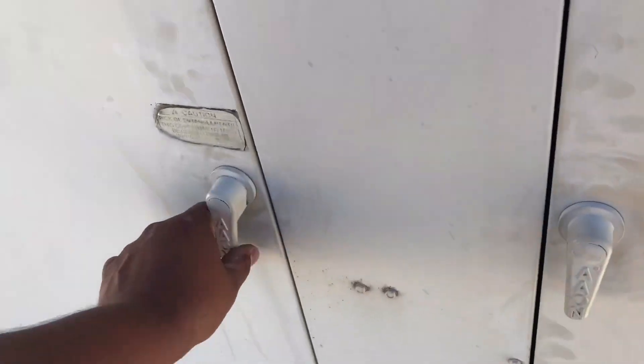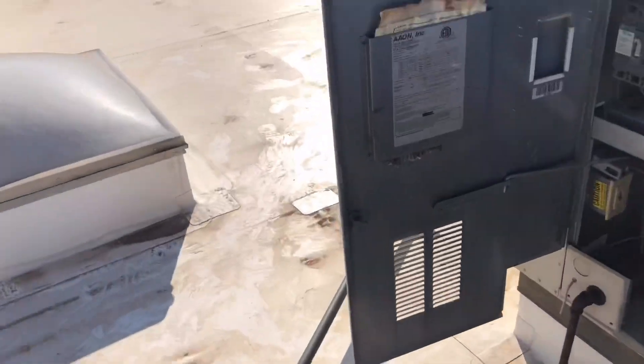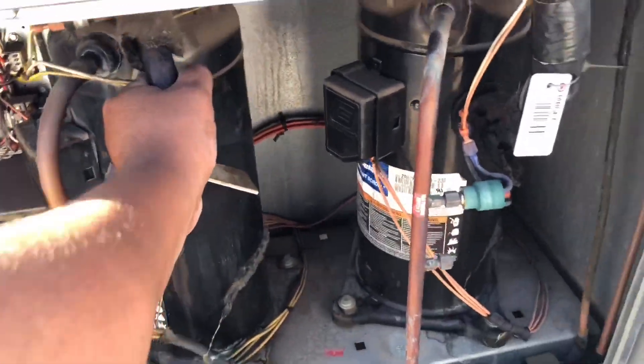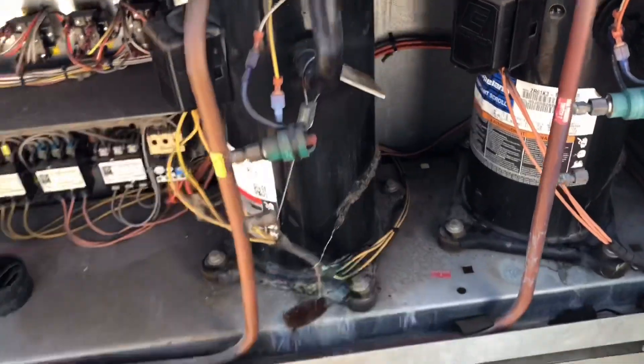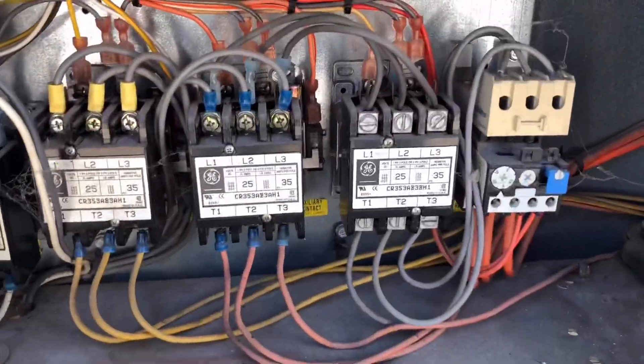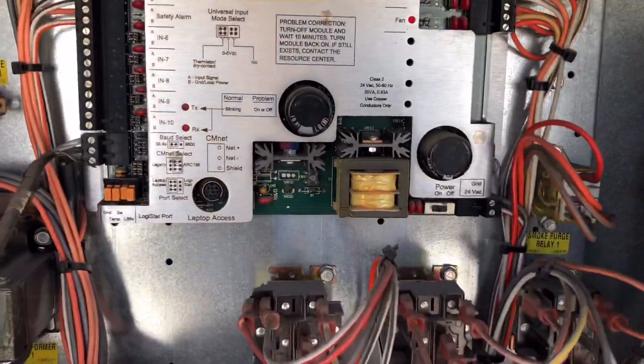We did manage to put our Fieldpiece probes in on the return, and we are showing a 20 degree delta T. Right now what I'm seeing is both compressors are running. I haven't hooked up any gauges and they both seem to be running fine. We are calling for cool 1 and cool 2 right there, so this unit is running pretty good.